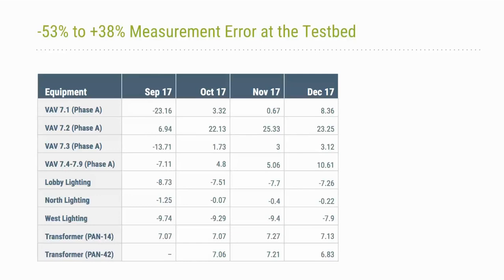In the case of the transformer, you see there's actually two rows. One says panel PAN 14 and PAN 42. The one on the bottom is the one that actually uses voltage taps. So in this case, there's a meter that is connected to a spur bracket on the panel, and it's aggregating the current and voltage to provide a better estimate of power. However, what happens here is that we didn't see much improvement from the standard PAN 14, and the standard is the one that I've described before, using just a wireless CT and no meter. There's no voltage tap for them, so you don't really have a measurement for voltage. It is just an estimated value at the beginning of the project, for example. And we didn't see much improvement on that. Next slide, please.